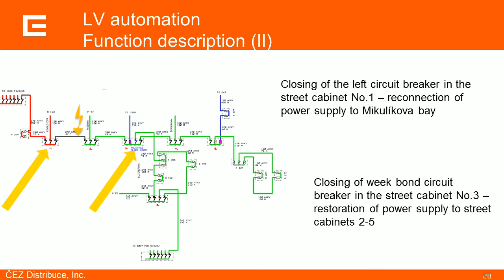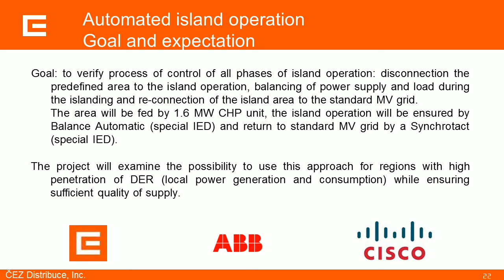Last but not least, the third objective is about island operation. Here we try to propose a control of all phases of the island operation, which means we want automatic disconnection from the grid of the part of the grid meant for island operation, then automated balance operation of the island, and then automated reconnection to the grid. We're doing this exercise because we want a proven solution for the grid once there are many more distributed energy resources connected to the grid in the Czech Republic.